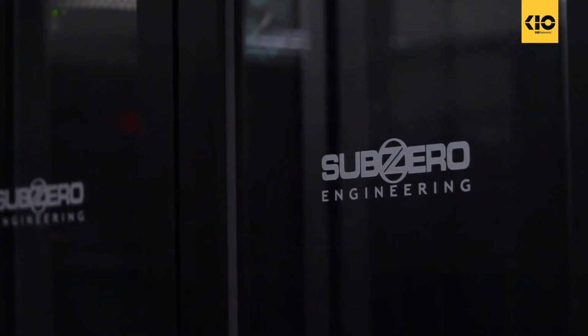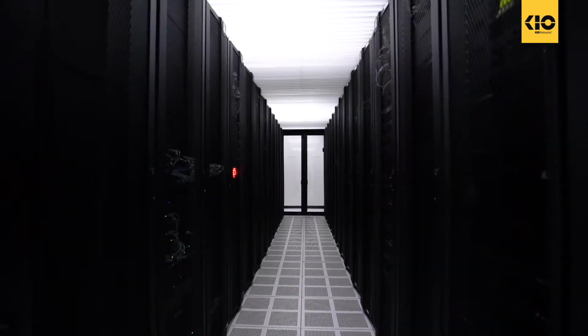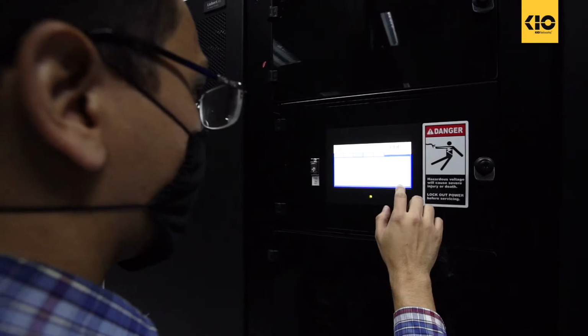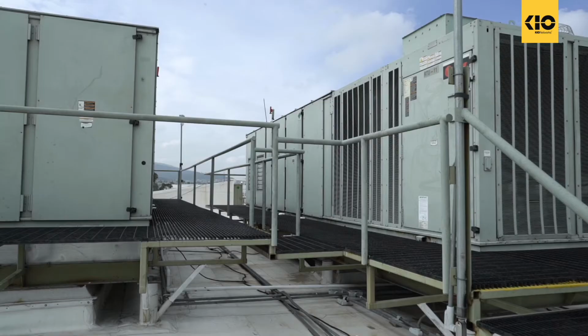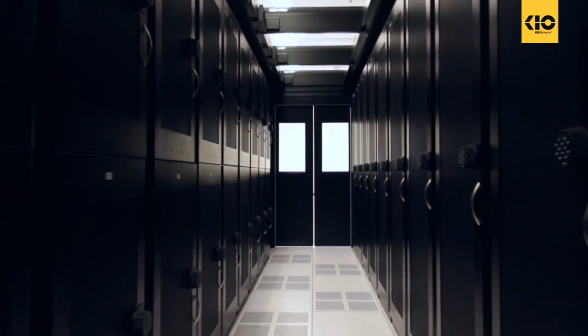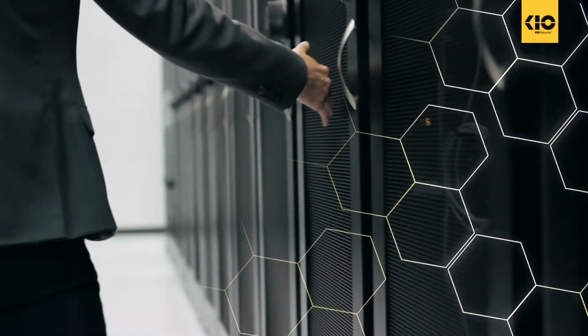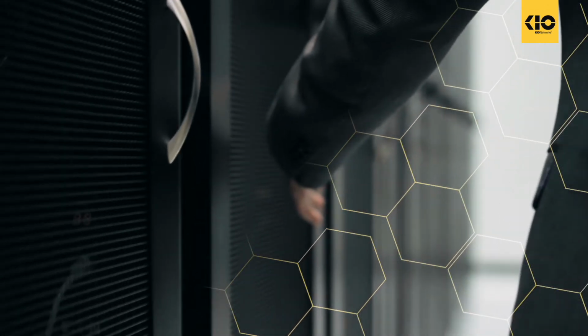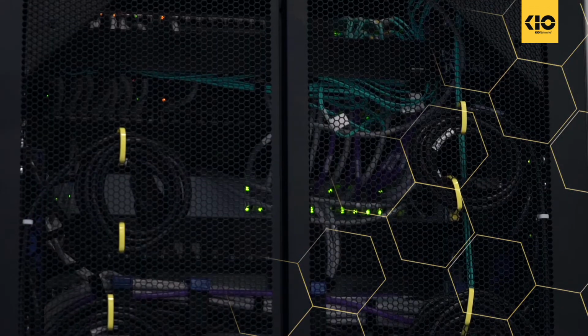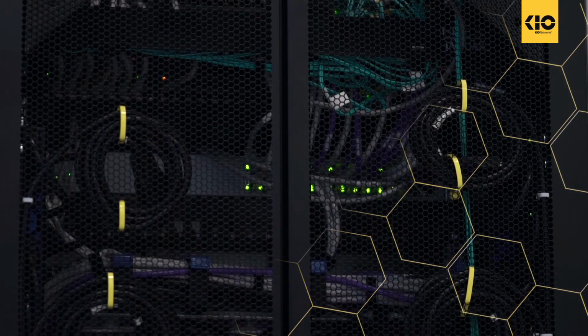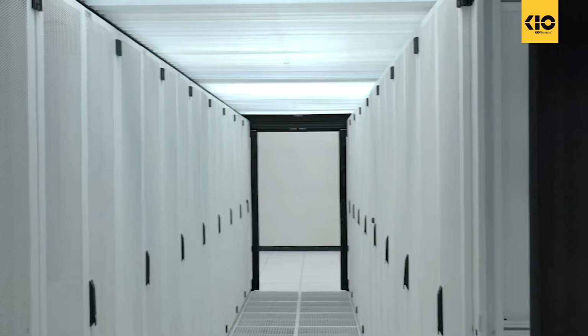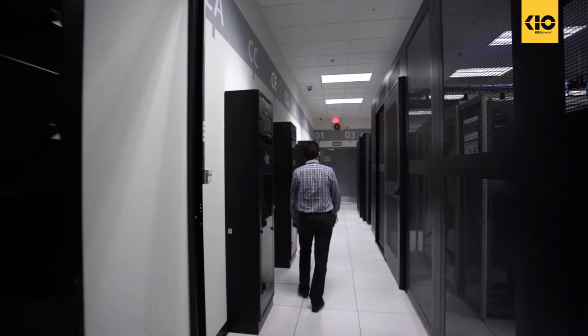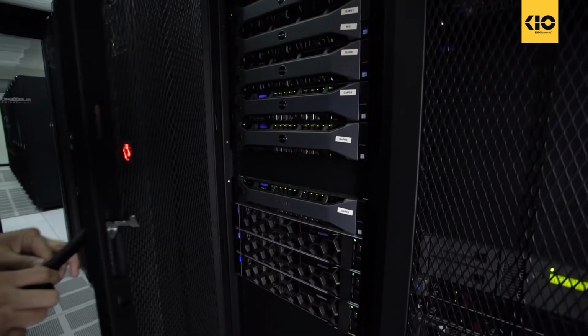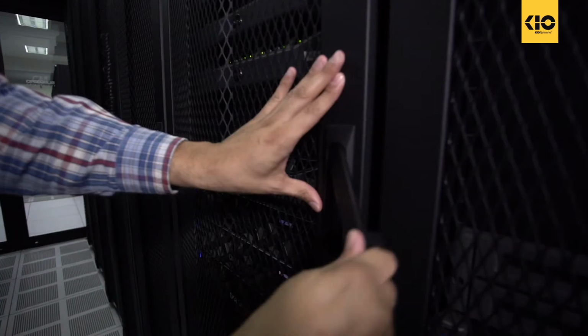To optimize the use of electrical energy, we have highly efficient cooling systems. We also maintain continuous improvement projects in air and cooling management. For example, we design and maintain cold aisle and hot aisle plans in the cabinet layout, supplying cold air to the front of the servers and removing hot air to the rear. Moreover, we implement cold aisle containment to avoid phenomena such as bypass and recirculation.